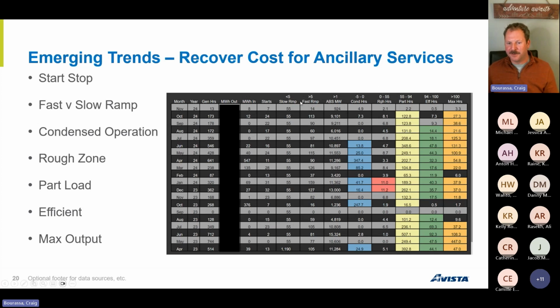I've worked with our designers and we've created codes to crunch out and look at voltages and breaker status, so we're able to determine if we have a fast ramp event going on. A fast ramp event affects your generator more than a slow ramp event—you go through a lot higher heat cycles, maybe the transformer too, if you don't have a low side breaker.